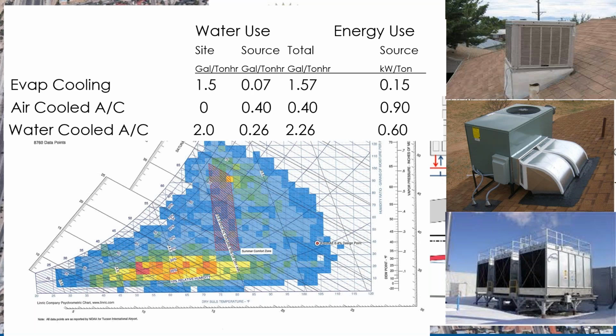One place we've seen great success is taking coil condensate water and using it as makeup water for a cooling tower. A number of university campuses have piping from all the buildings to collect coil condensate, route it back to the central plant, and pour it into the cooling tower basin, which requires no regulatory issues and is quite easy to do.